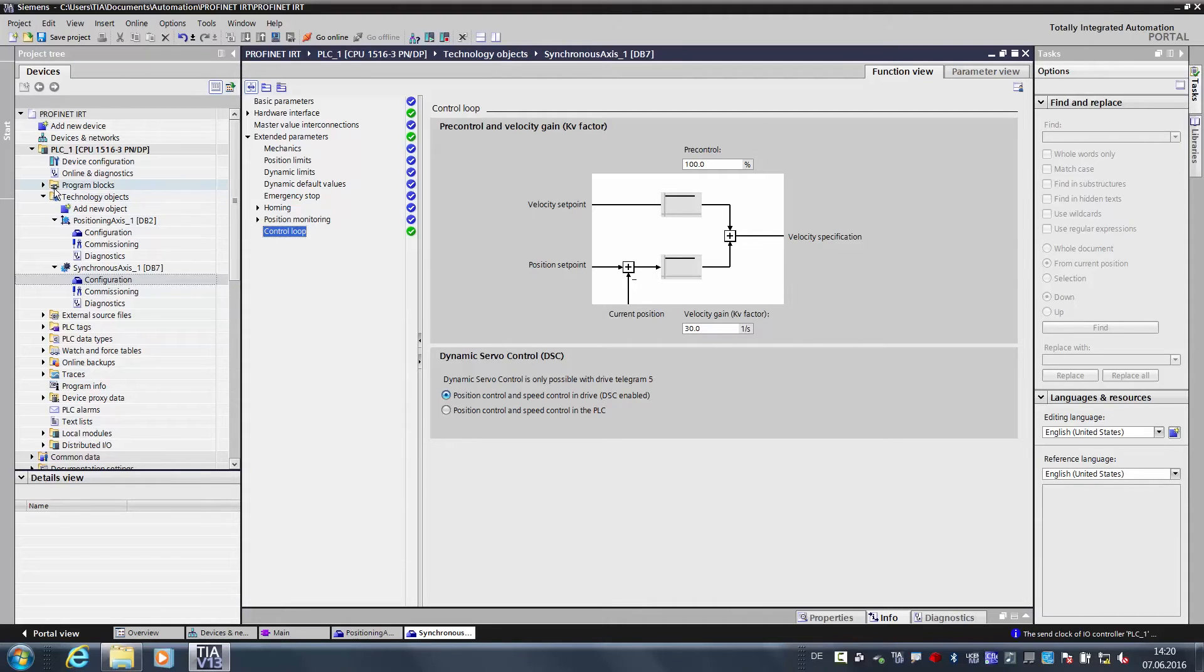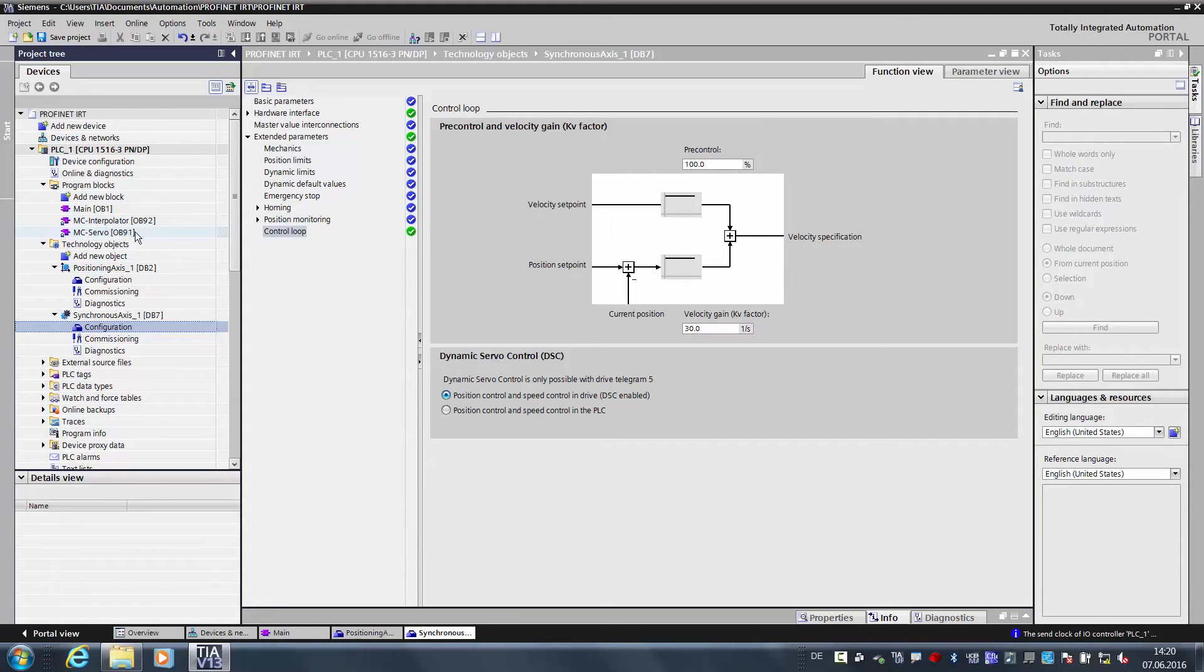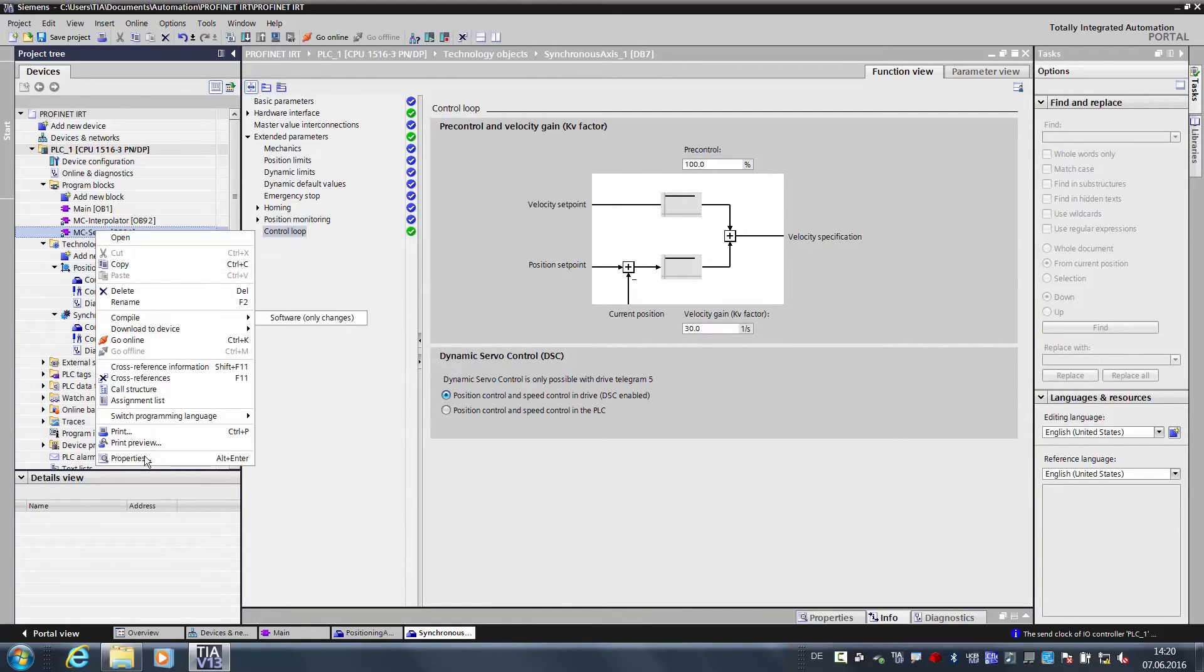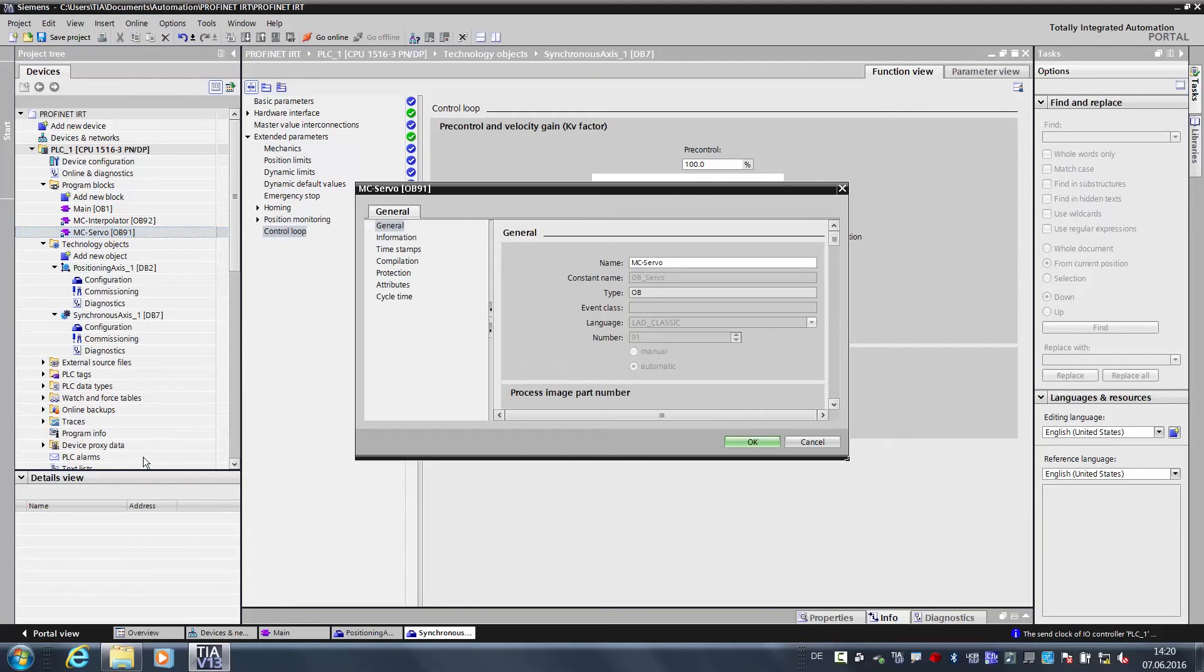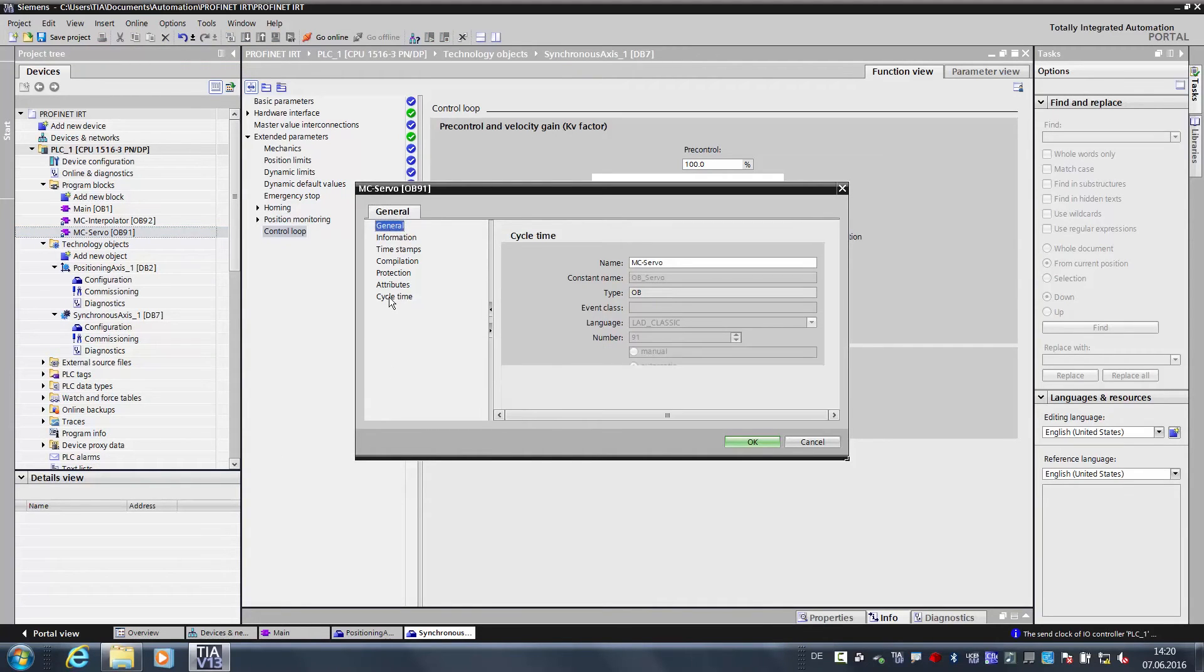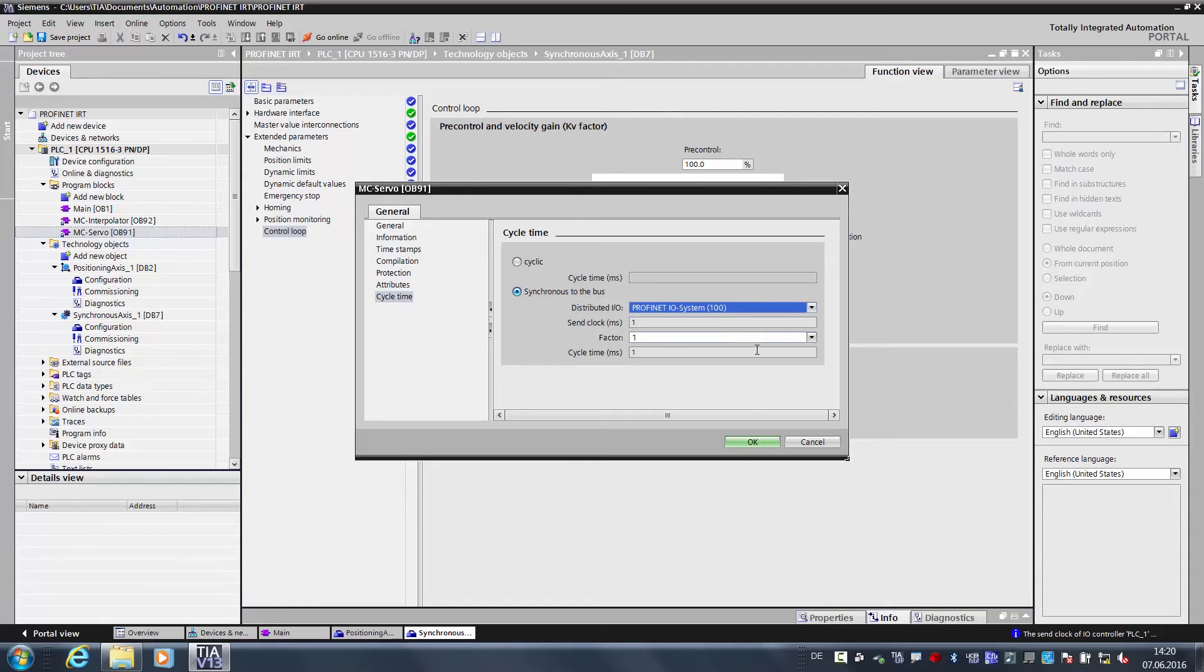Now we have created both technology objects, and we now open the program blocks. With the program blocks, you can see that thanks to the technology objects, two organization blocks have been created automatically. On the one hand is the MC servo, and on the other the MC interpolator. These are intended to run at the same cycle as our bus, and that is why I open the properties of the MC servo, go to the cycle time, and I adjust the cycle time specifically to our PROFINET system.